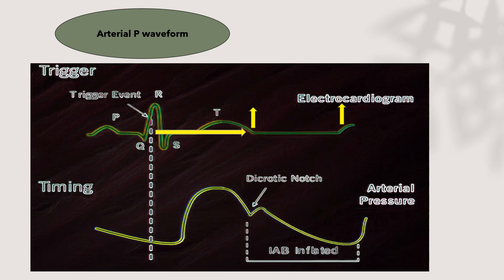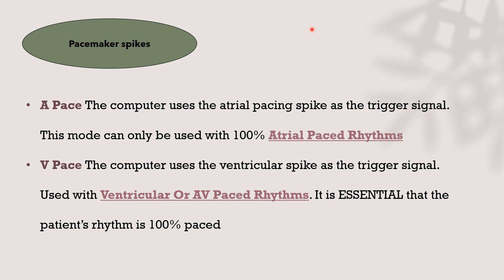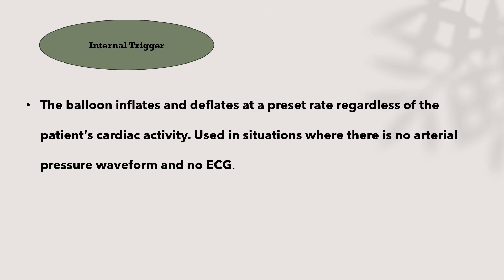As mentioned, the electrical impulse usually precedes the mechanical impulse. Pacemaker spikes are not preferred as a trigger except with consistent pacing. For atrial pacing, atrial pacing spikes are used as the trigger signal only in 100% atrial pacing rhythm. For ventricular or AV pacing, ventricular spikes are used, and the patient must also be 100% paced. The internal trigger inflates and deflates at a preset rate regardless of the patient's cardiac activity, usable when there is no arterial pressure waveform and no ECG — typically set at 40–120 bpm, usually 80 bpm.